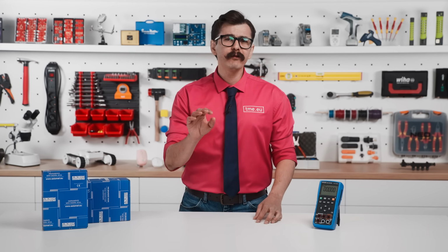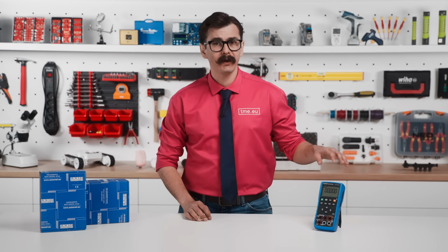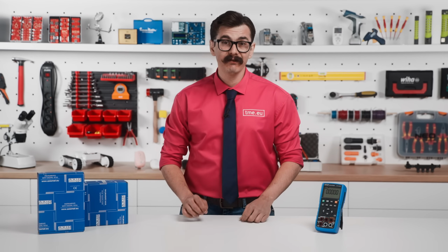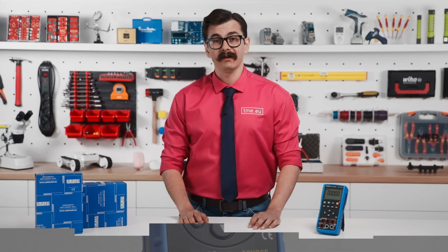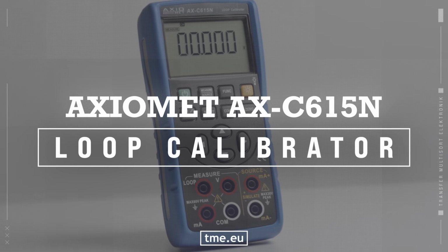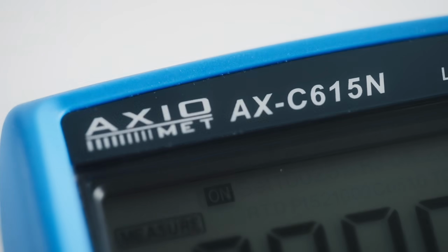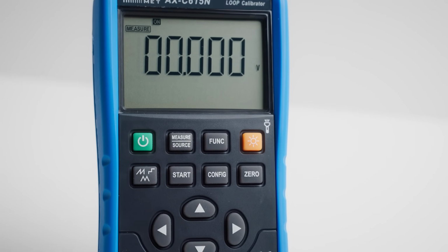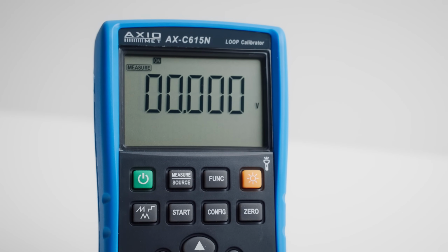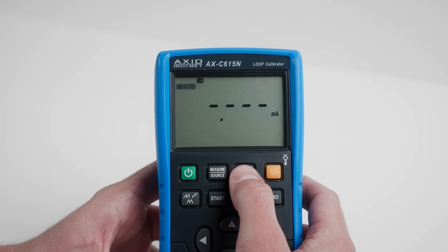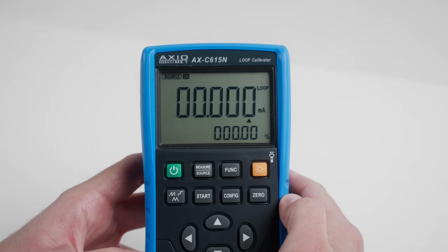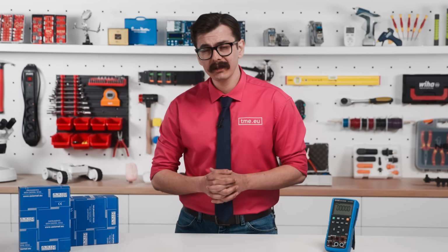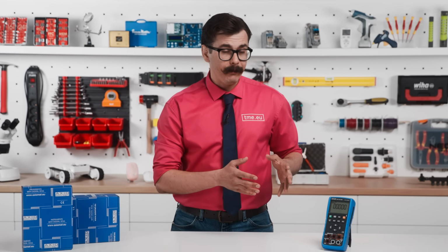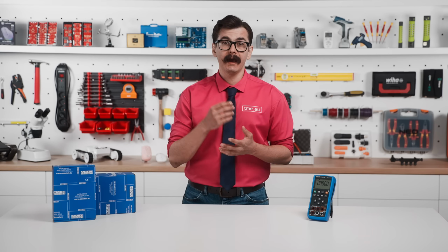So today we are looking at a professional tool designed to verify your 4 to 20 mA loops, the AX-C615N Loop Calibrator from Axiomet. This handheld loop calibrator is designed for testing, simulating and powering 4 to 20 mA current loops, the standard communication method in industrial automation. It can measure DC current and DC voltage, source a precise current signal, simulate a transmitter, and it also provides an internal 24 volts loop power supply. This means that you can power and test two-wire transmitters directly without needing an external supply.